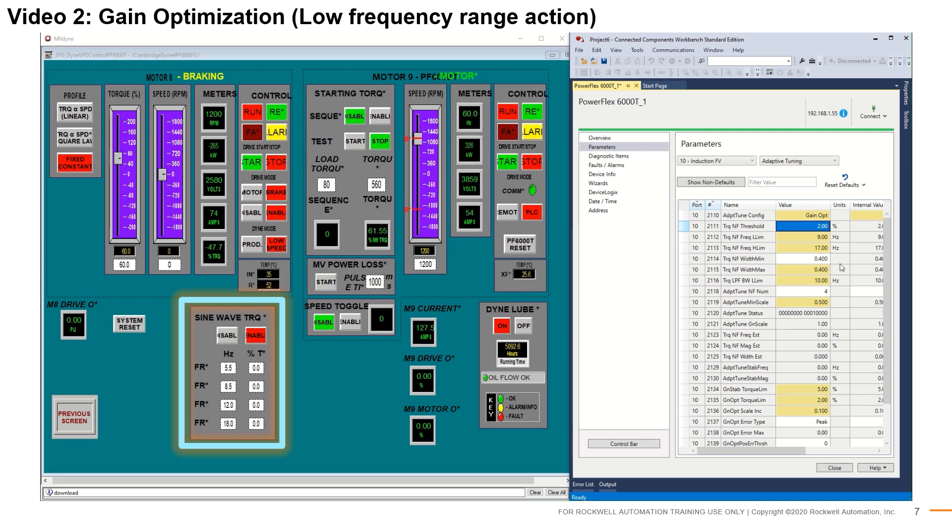Note that the moment adaptive tuning is enabled in gain optimization mode, the regulator gain scalar starts to increase. Its value can be observed using parameter number 2121 adaptive tuning gain scale. This scalar starts at the value of 1 and rises in increments set by parameter number 2136. The lower and upper bounds of this scaling factor can be configured using parameter number 2119 and 2141. For now, the upper limit is set to be 2 or 2 times the existing system bandwidth.